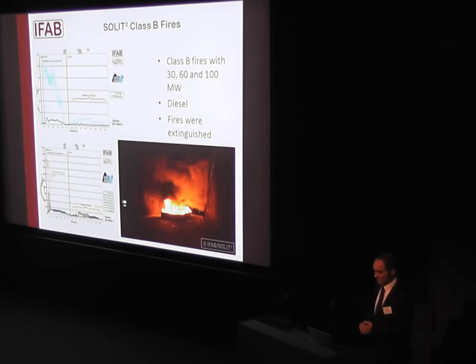When you look at the curves, the top graph is showing the heat release rate, and then you can say, okay, you started the water mist system with 30 megawatt, and then, strange, the heat release rate was increased to 60 megawatt. You have to know a little bit more details about the measurement system, how you measure the heat release rate in such fire tests. It's not that easy. You measure it by calculating it from the oxygen consumption of the fire.